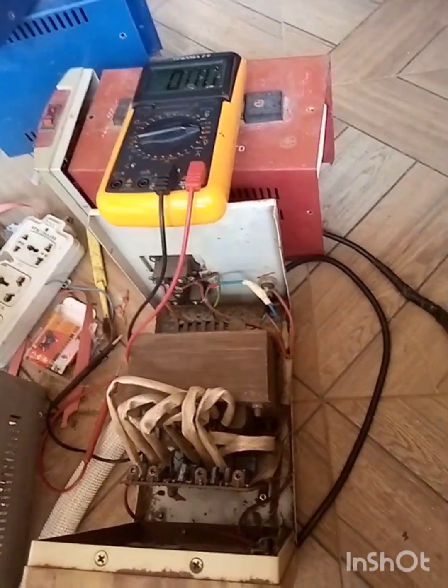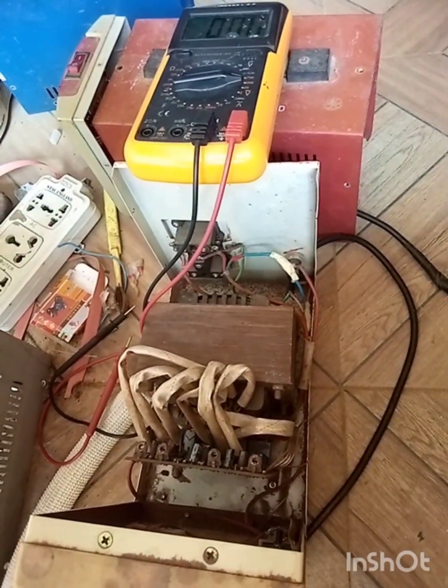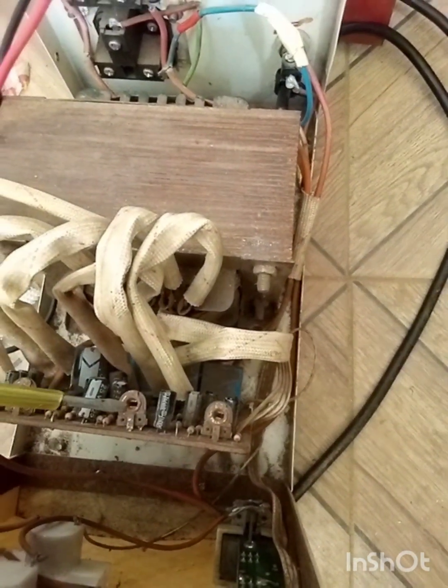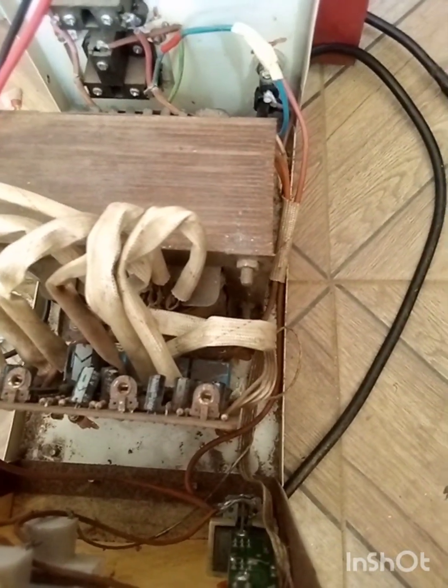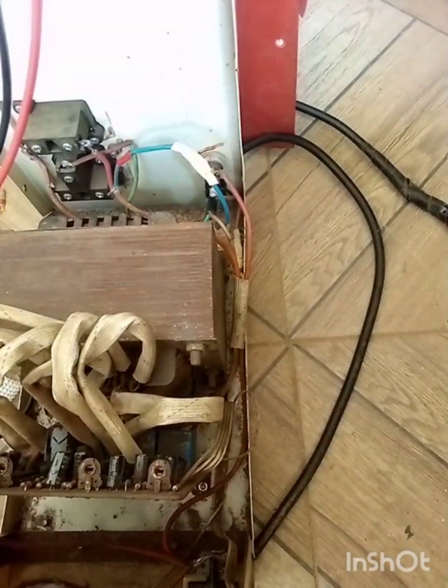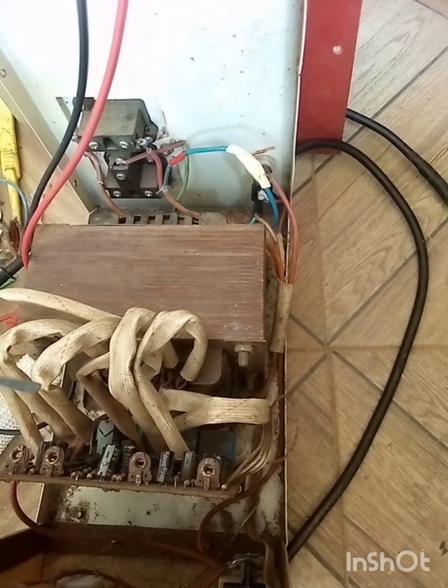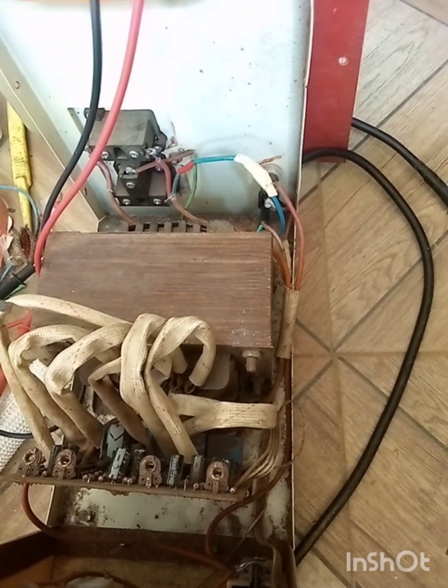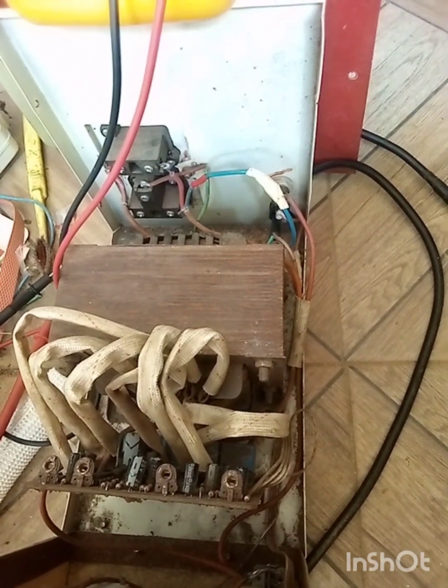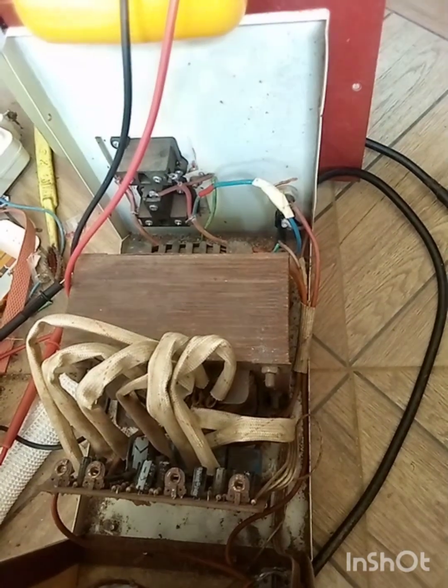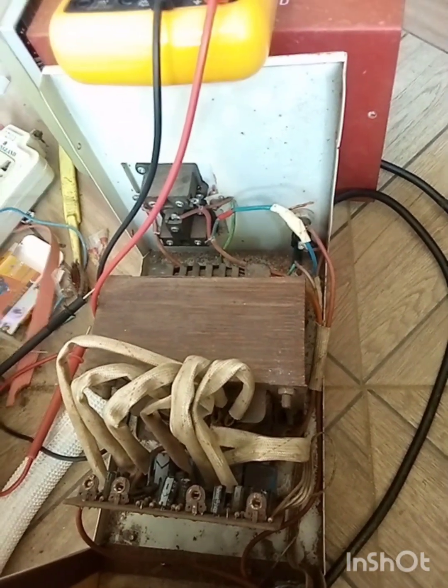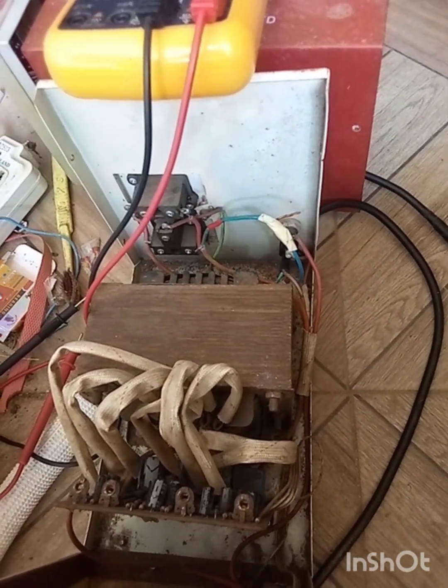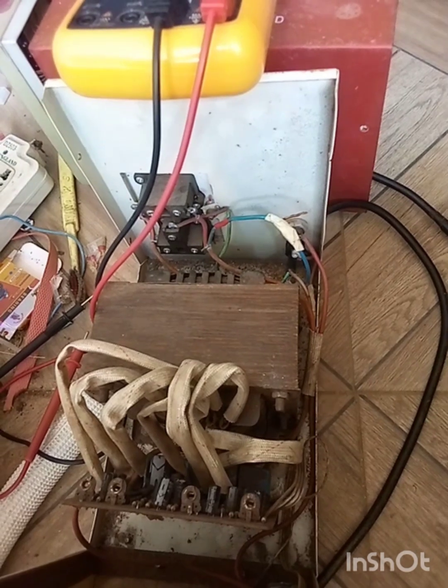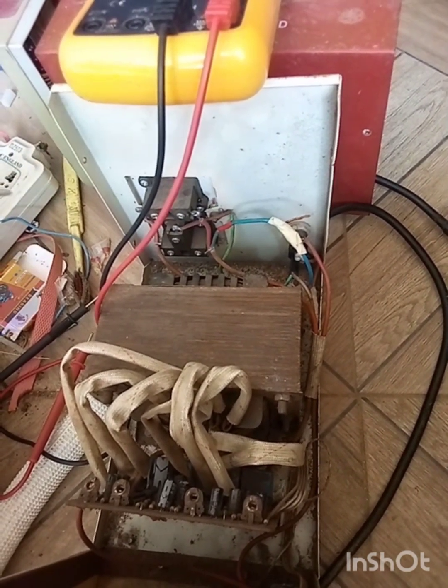I told you people that what we have to do to this stabilizer now to stabilize the voltage is to set it from the variable resistance. As you can see, we have 5 variable resistors here. Initially, this stabilizer's voltage was at 290, which is very wrong. We want to make sure the voltage is not more than 240 and not less than, say, 220 or 200. The accurate voltage this stabilizer should be is in the range of 220, 230, 235, 240, not higher than 240.